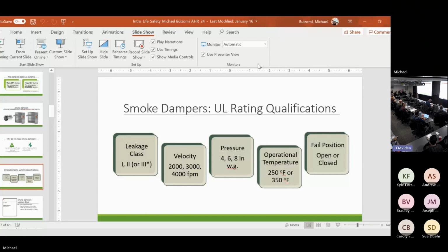All you've done is, let's say that was a 24 by 24 damper. I have a UL listing to close a 24 by 24 damper with an 18-inch pound actuator at 250 degrees Fahrenheit, 2,000 feet per minute, 4 inches. Now we're going to do what we call the trash can spec. We want the biggest and baddest thing you guys offer. We're going to put class 1, 4,000 feet per minute, 8 inches, 350. All I did was change the actuator from an 18-inch pound actuator to a 175 inch pound actuator, taking the cost of that actuator from, let's just say, $100 to $600 on every single damper for no reason whatsoever. You didn't increase the life safety of your building. So if you are specifying high velocity and pressure ratings on dampers, make sure it's for a good reason.